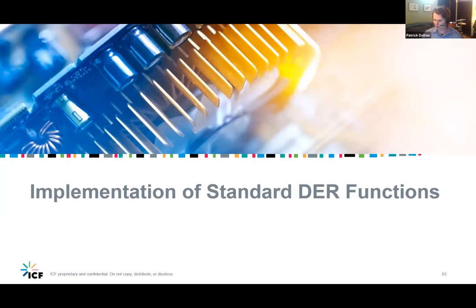Then the last question I'm seeing here is, what is the impact of DER in terms of harmonics? I would just say that there are harmonic requirements. There's a whole power quality section in 1547 that we're just not going into based on time, and that includes harmonics, voltage, steady state voltage fluctuation, DC injection, and, I'm sure I'm missing something there, consecutive event ride through. So, brief events that don't qualify for tripping. A number of different topics are addressed in power quality, including harmonics. And the harmonics section is somewhat related to IEEE 519, which is the recommended practices for harmonics.